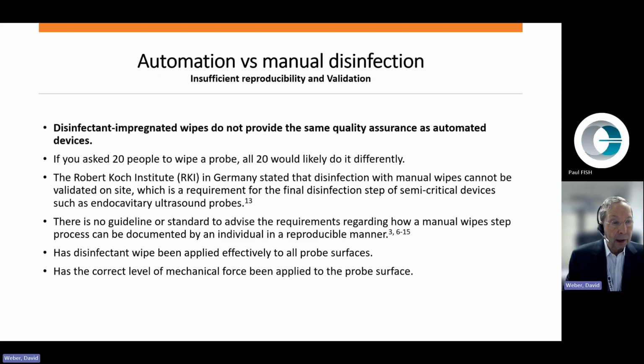There is no guideline or standard to advise the requirements regarding how a manual wipe step process can be documented by an individual in a reproducible manner. Has the disinfectant wipe been applied effectively to all probe surfaces? Has the correct level of mechanical force been applied to all probe surfaces? In addition, has the appropriate time been documented?